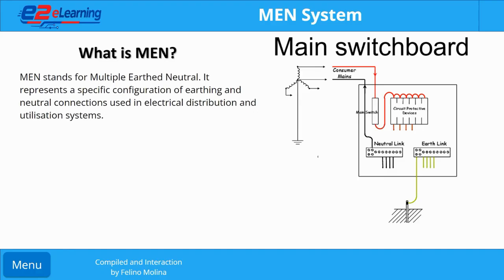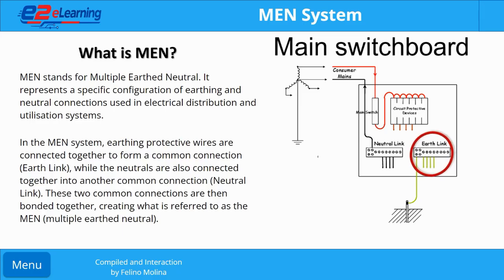MEN stands for multiple earth neutral. It represents a specific configuration of earthing and neutral connections used in electrical distribution and utilization systems. In the MEN system, earthing protective wires are connected together to form a common connection, while the neutrals are also connected together into another common connection. These two common connections are then bonded together, creating what is referred to as the MEN, multiple earth neutral.